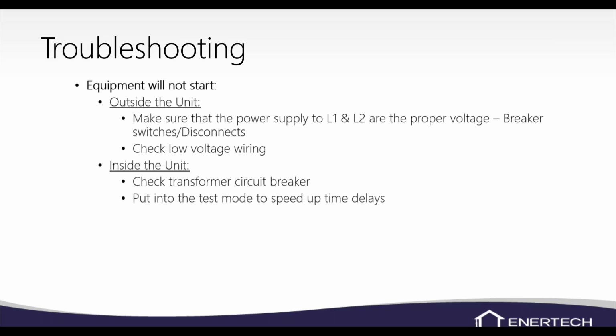After 1 hour, it'll realize that you forgot to put it back into normal mode with the time delays, and it'll revert back to its time delays. The status light will stay out on the lockout board, but it will revert back to its normal time delays. You may want to make a note to put that back in next time you're out there, but there's not a huge need to make a special trip. Just a little side note on the test.